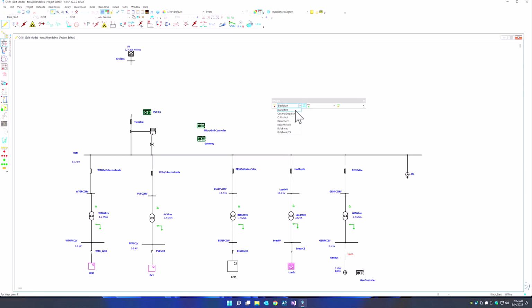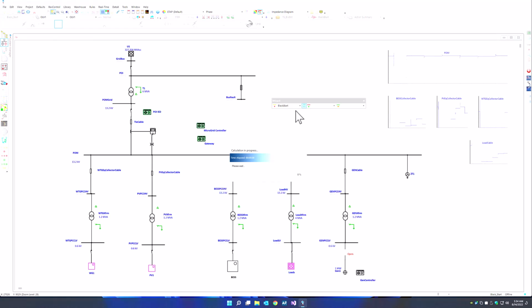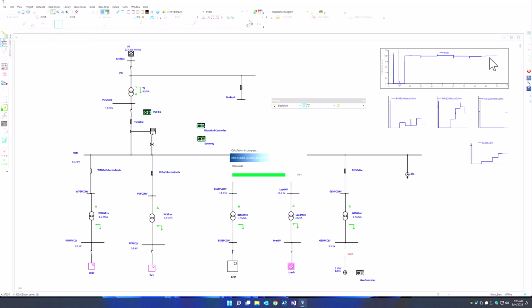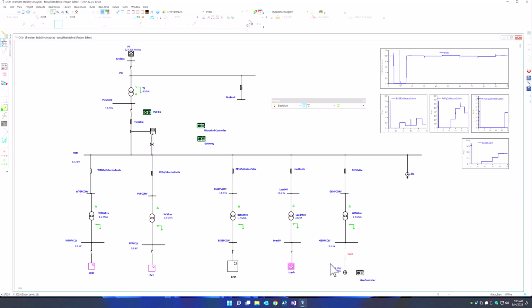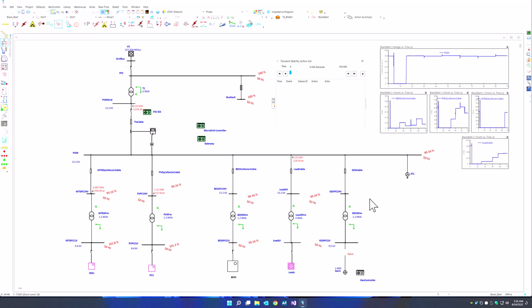We can simply put our controllers in place, set about the parameterization, bring up our plot views, and run the simulation. And as these controllers take various effect within the system to control the wind, solar, energy storage, adjust them based on the loads, and dispatch synchronous machines in the system, you can see the response and behavior on our dynamic live plot views. And the plot views are essentially telling us we had a brief disconnection from the system, and we're black starting this network back again using our energy storage, PV, wind, and our synchronous generator such that we can serve the load within the network.